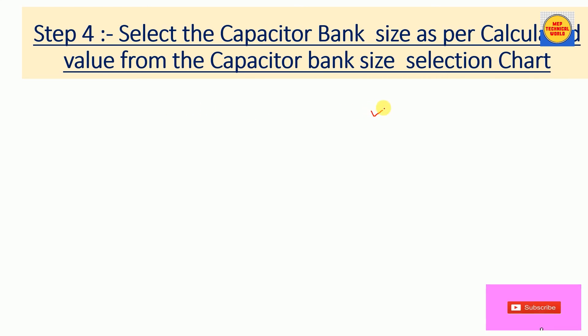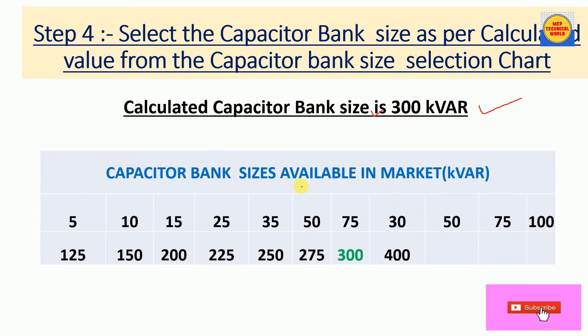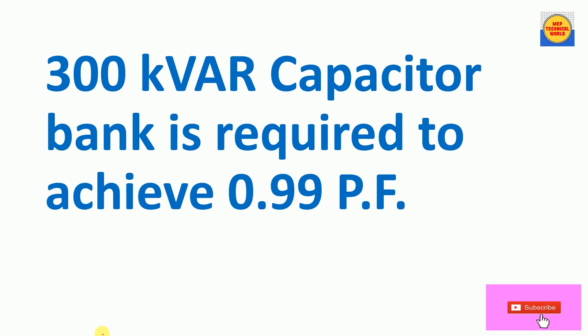Here we have the capacitor bank sizes available in the market on the selection chart. We compare our calculated value of 300 kVAR with the chart. We always select a value equal to or above the calculated value — never below. Here we have exactly 300 kVAR available, so our final proposed capacitor bank size is 300 kVAR.